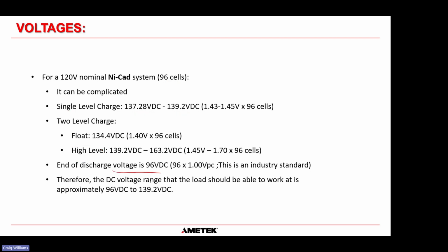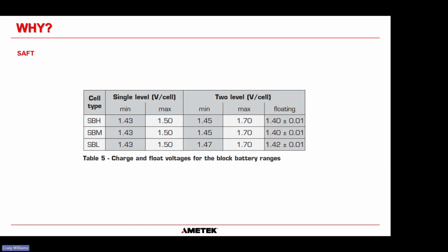And the end of discharge voltage is 96 cells times 1 volt per cell. That's an industry standard, so it's 96 volts. So the DC voltage range that your load should be able to work at is 96 volts all the way up to 139.2 for this single level system. Okay, that is for a NiCad battery.